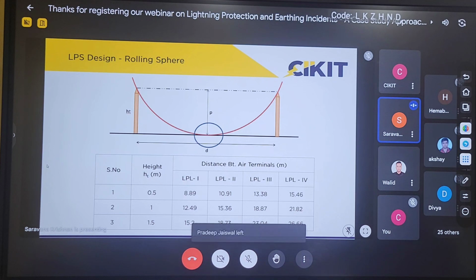We have performed the calculation using the formula for different heights: 0.5 meters, 1 meter and 1.5 meters. Based upon this calculation, we have to place the air terminals accordingly. The distances provided here are the maximum distances. It is not the actual distance, it is the maximum distance that has to be provided between these air terminals. So if I am placing the air terminals in the form of a rectangle, then the maximum distance will be the diagonal distance and not the length or width.